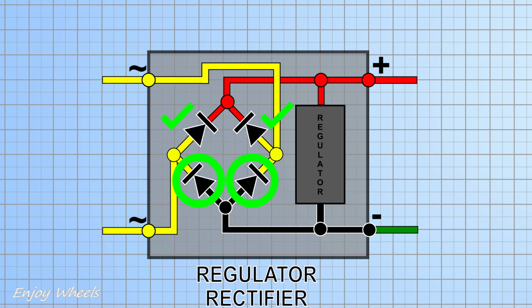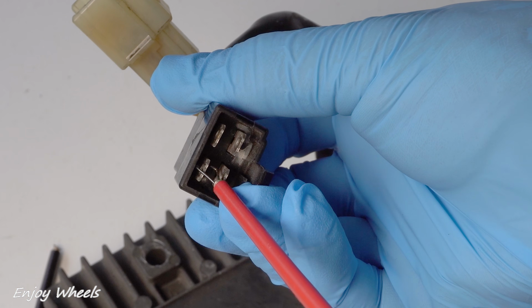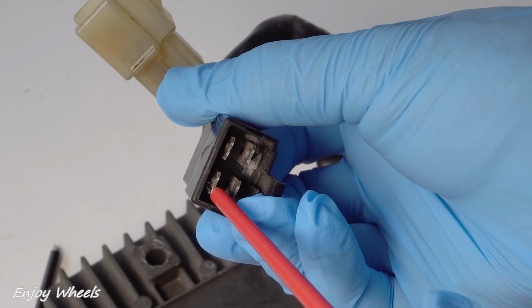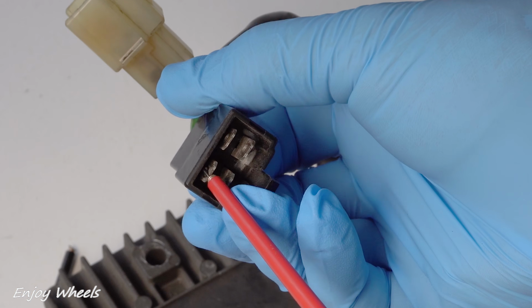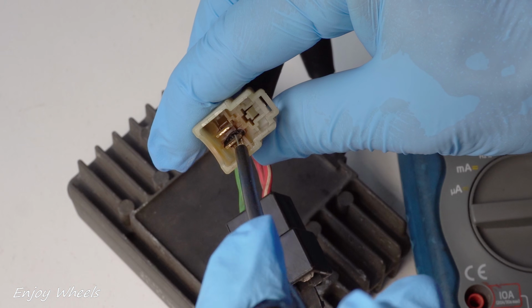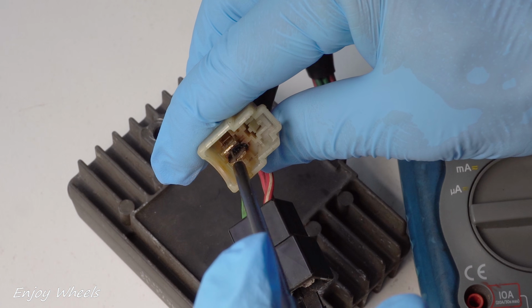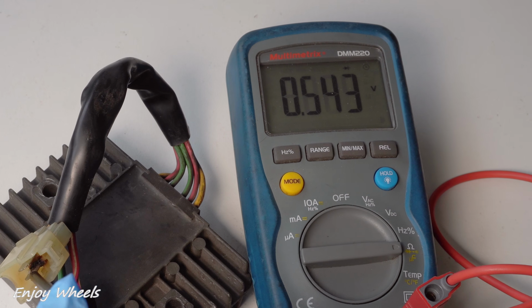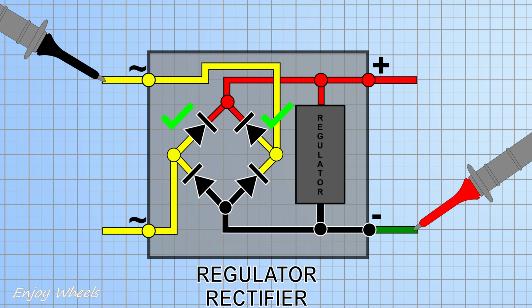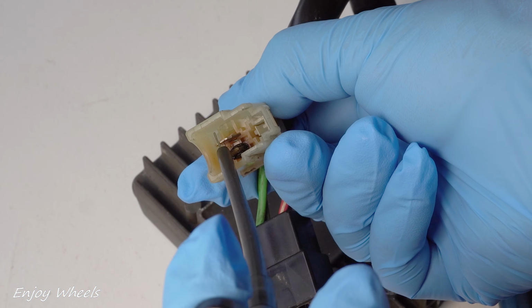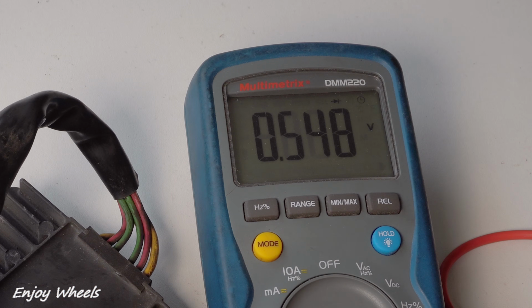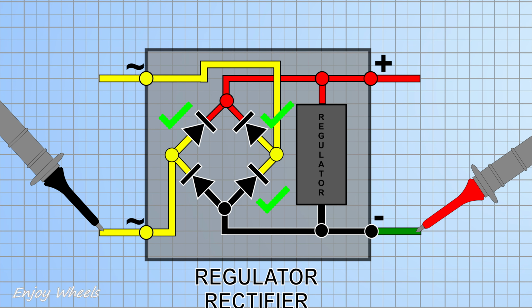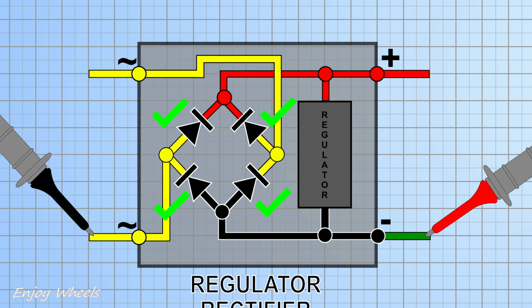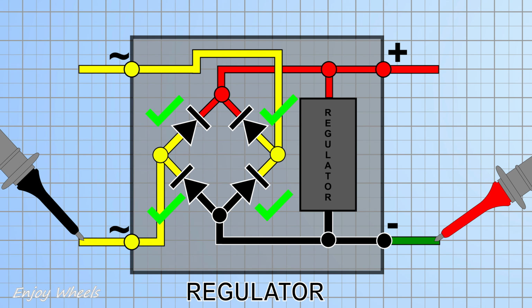Now I'll test the 2 diodes in the lower section of the diode bridge. I connect the V+ lead to one of the 2 green wires, the anodes of the 2 diodes, then connect the COM lead to the cathode of one diode: 0.54 volts, that's good. The other diode reads 0.55 volts, also good. All 4 diodes in the bridge are good, so the rectifier section is working properly.